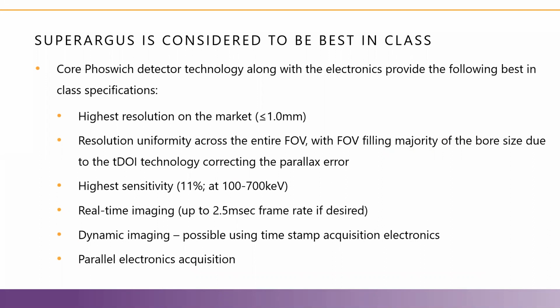Now, the Super Argus system is considered best in class for many reasons. Firstly are those unique Phoswich detectors that I mentioned. These are composed of 2 different phosphors sandwiched together, so hence the term phoswich. And these detectors are used in both the compact and the Super Argus systems and really provide true depth of interaction information and thus contribute to many of the other unique features of the system, including high resolution, resolution uniformity across the entire field of view, which is really important, as well as improved sensitivity.